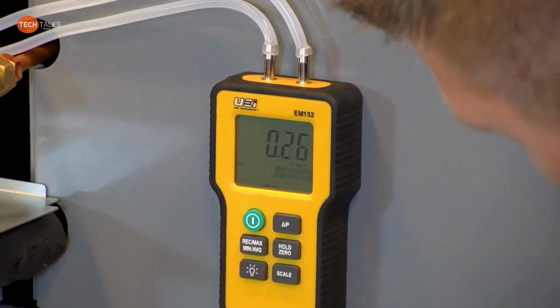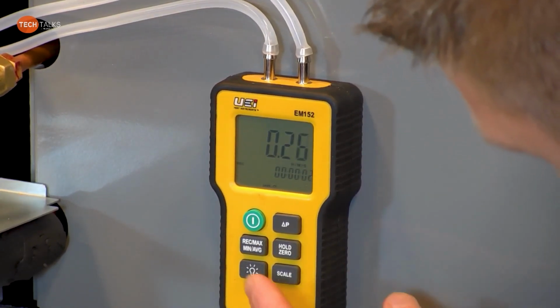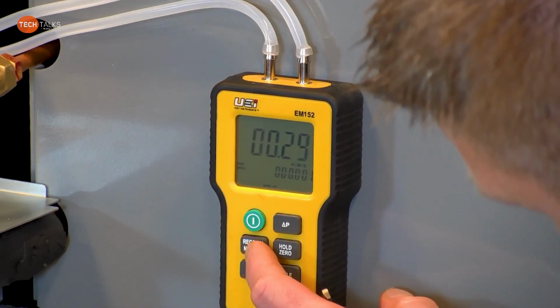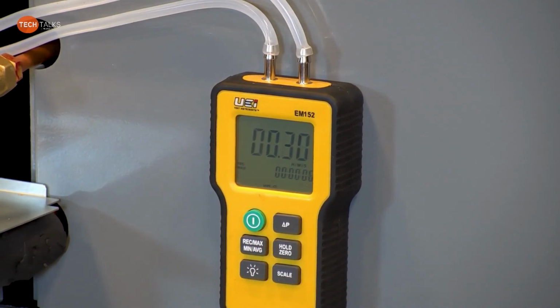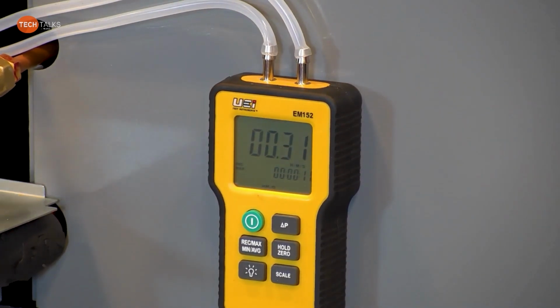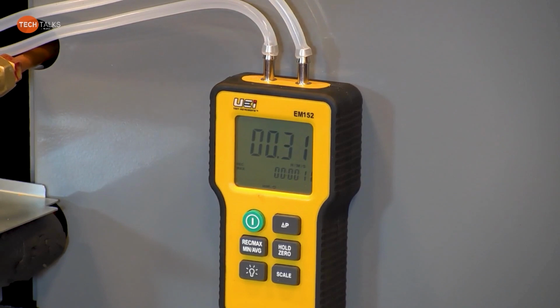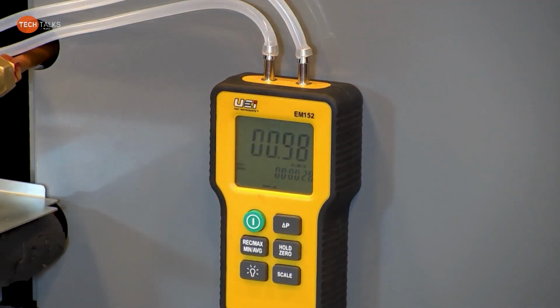GREE uses 230 volt reversing valves. So when you're using a 230 volt reversing valve, the board is actually controlling when that reversing valve is energized, okay? What GREE actually does, even though it's in heat mode, and the machine knows it's in heat mode with a 24 volt call, it starts that unit up, runs for a minute, then it engages the reversing valve. That reversing valve is not energized the entire time. So it's not until you get a call, compressor actually starts running for a little bit, then it goes up.